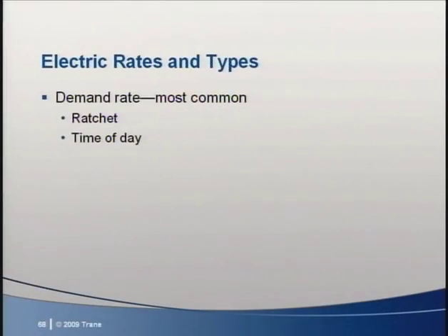They tend to vary. Some might have a time of day energy price, but most don't. A common myth about ICE energy storage is that time of day rates with low nighttime kilowatt hour charges are needed to make the economics work. That's not the case. Most of the ICE storage projects do not have time of day rates.